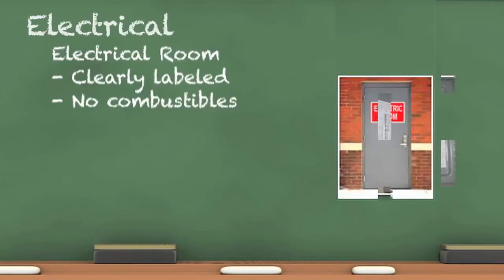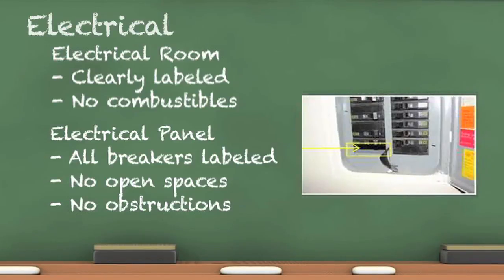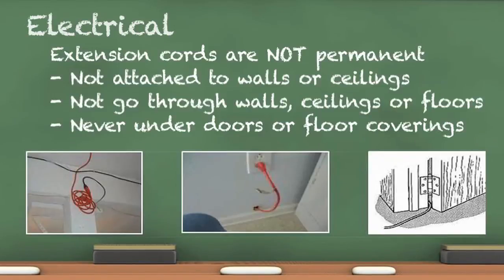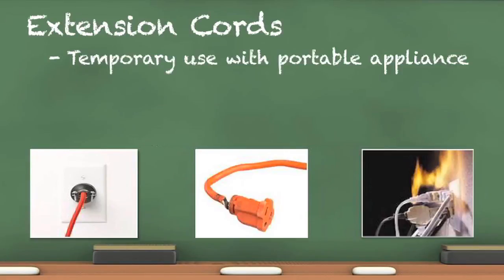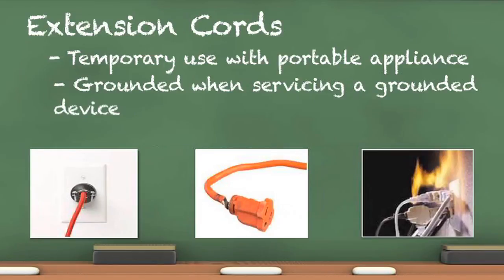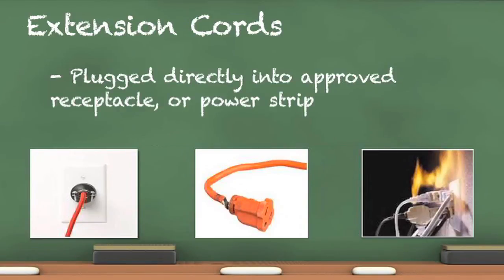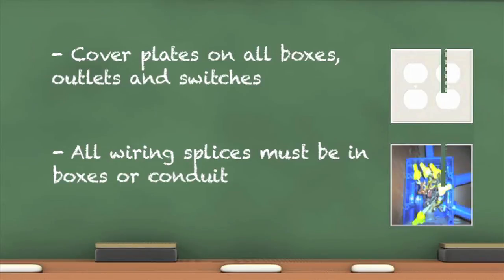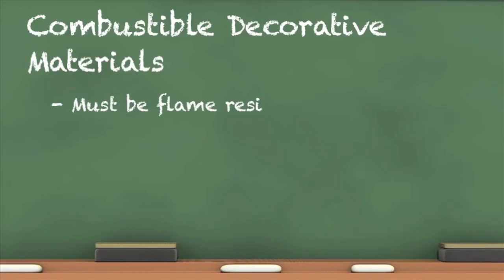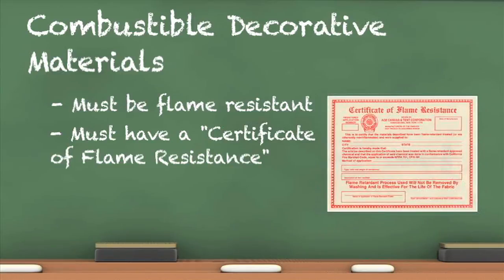Electrical rooms and panels must be free of combustibles. All breakers must be labeled either by labeling each switch or completing the panel schedule. All open spaces are required to have approved blanks or covers. Extension cords may not be affixed to or go through walls and ceilings, shall not be placed under flooring of any kind, and are for temporary use with portable appliances only. When the portable device being powered is grounded, the extension cord should be grounded as well. Extension cords must be plugged directly into a wall outlet or power strip with surge protection and may power only one portable device at a time. Cover plates must be in good condition and completely cover the outlet, switch, or box. Combustible decorative materials are required to be inherently flame resistant or treated to be flame resistant.